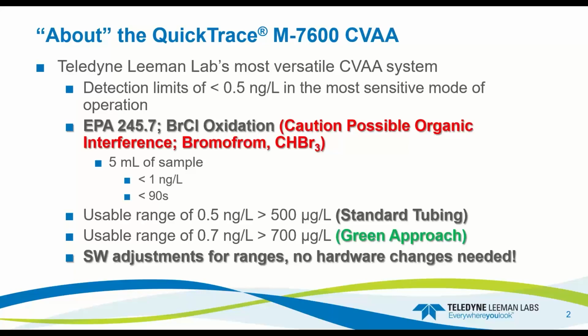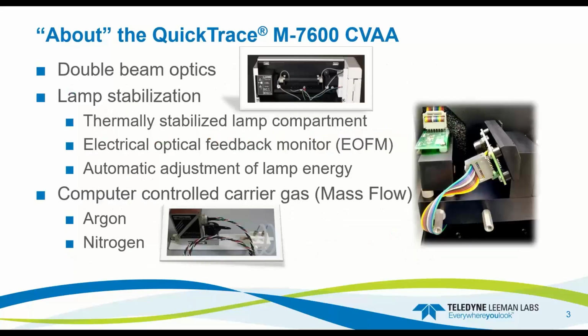The normal usable range on the system is 0.5 to 500 ppb, and that's with our standard tubing. For the new tubing, which we're going to discuss here shortly, it changes just slightly. The bottom end goes maybe around 0.7 ppt, and the higher end can increase up to about 700 ppb or 0.7 milligrams per liter. And we do all this without any hardware changes. So you're changing the software ranges, you're bringing in the new tubing, and you're doing it all through the software without making any hardware changes at all to the system.